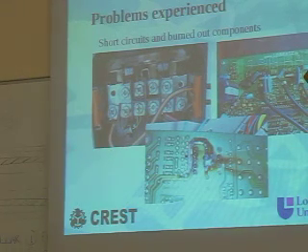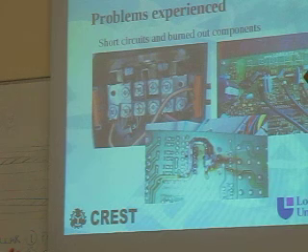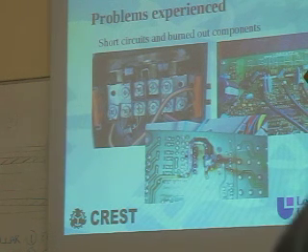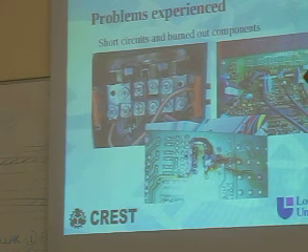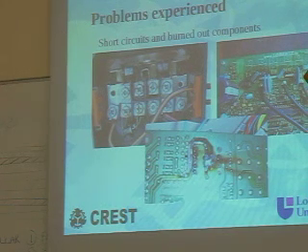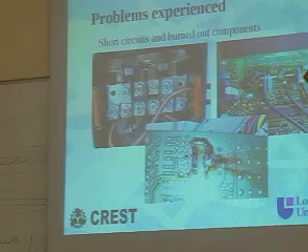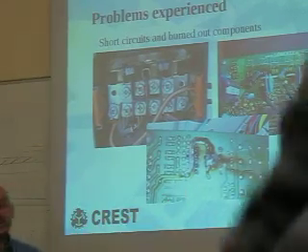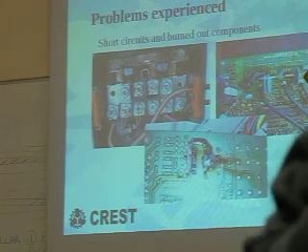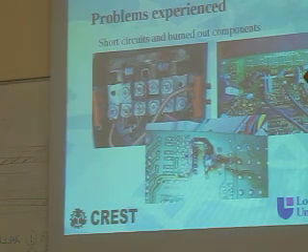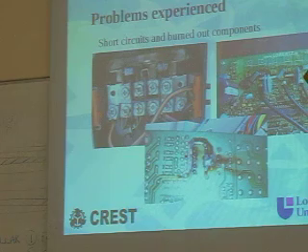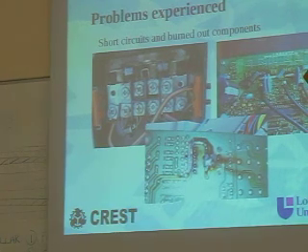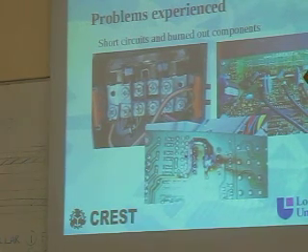This was the first photovoltaic system we saw there, where they tried to do battery charging and they put the terminals on the wrong way around, but they hadn't used a fuse, and so it had blown the diodes in there, rectifier diodes. And this was something I travelled a long way to replace, this board in the electronic load controller. I got this brand new board, came over from Indonesia. I had asked them to test it. We had no test facilities. They said, yes, this has been tested.